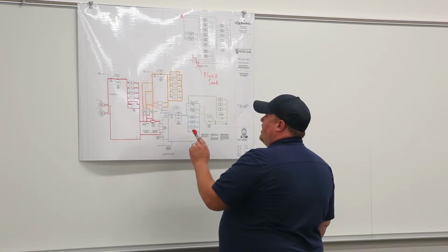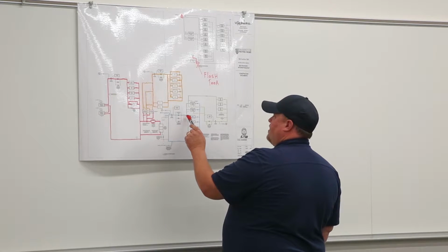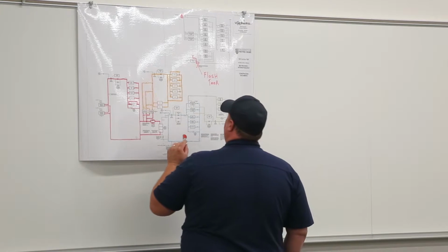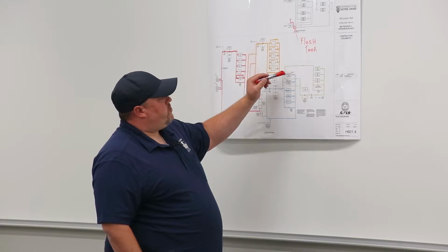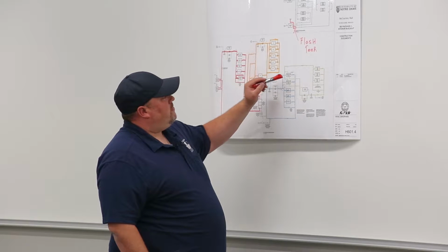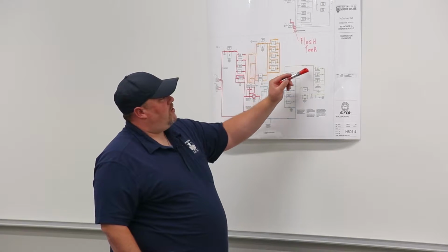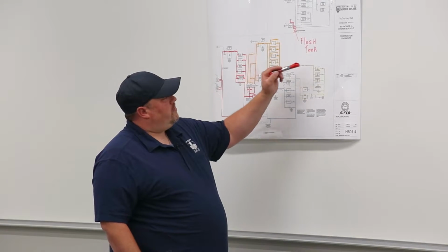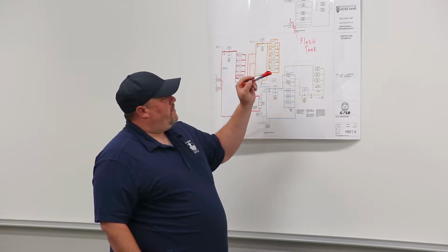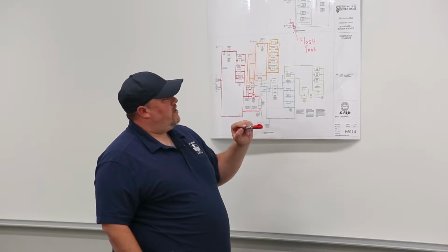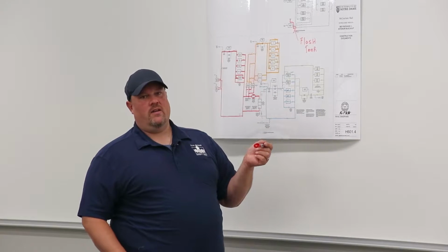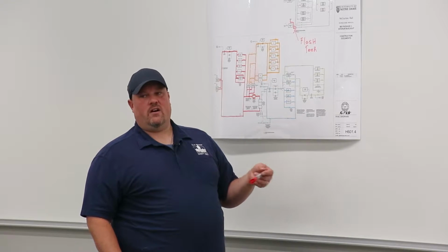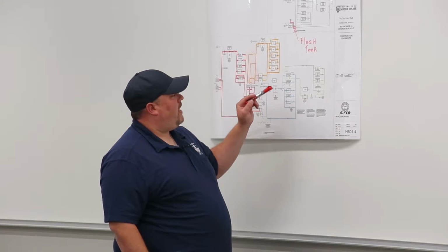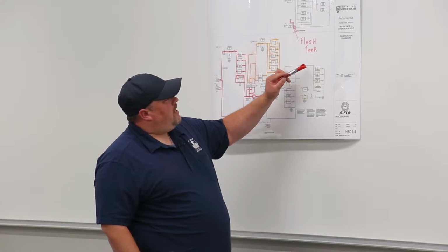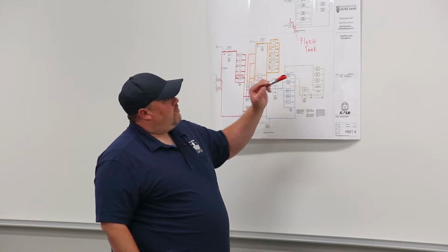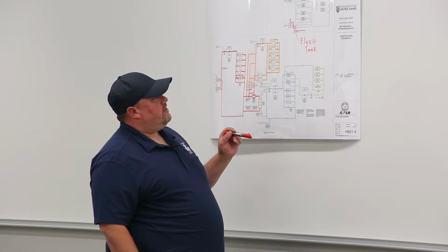As it goes through the pumps here, we've got several checks. It does a basic loop through the processed chilled water heat exchangers, and in turn transfers that cooling through these heat exchangers to our processed chilled water loop. The processed chilled water loop goes around to each lab, and it's got its own set of pumps, its own air and dirt separator that also needs to be blown down in 1-month intervals for the first year and then 6 months after that. And the processed chilled water loop has drops in each lab with a basic valve bypass.